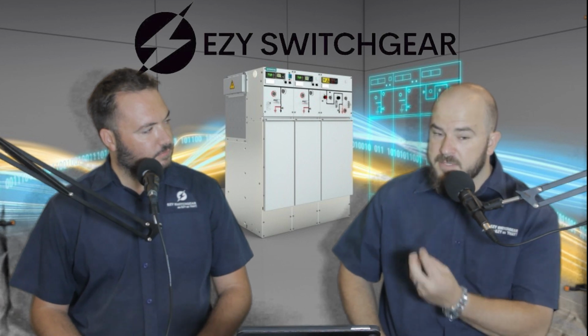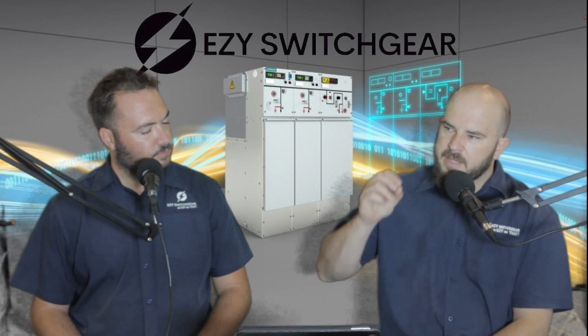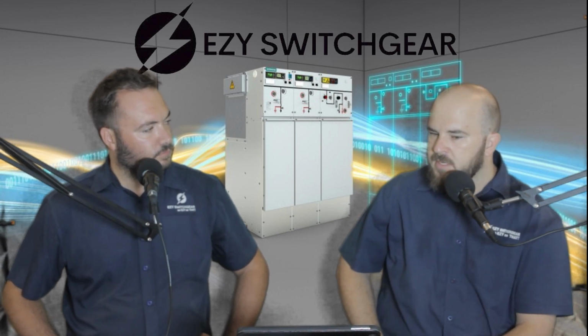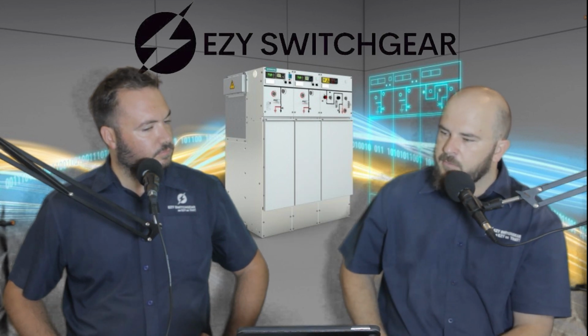And now that thing is faulty. That equipment that you just plugged in is faulty, and now there's an overcurrent that's being created. Now, where do you want that overcurrent to trip? Do you want it to trip as close as possible to it, or do you want to trip out the whole town?